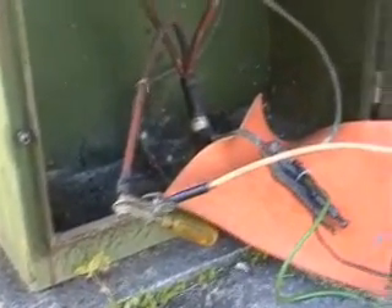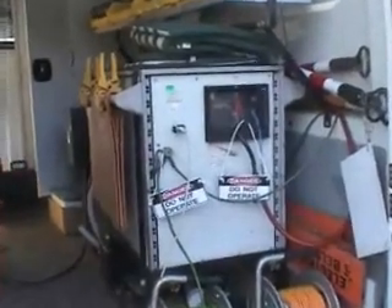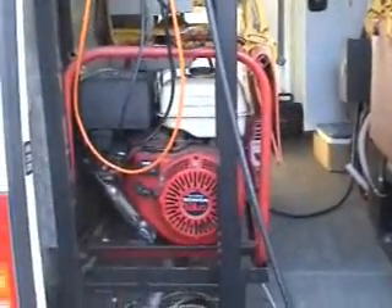We have the positive from the thumper and the ground cable on the earth. This is the big thumper, which goes up to 32 kV, running off a very noisy generator.